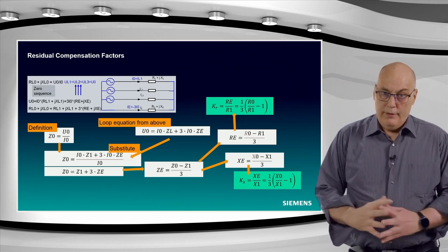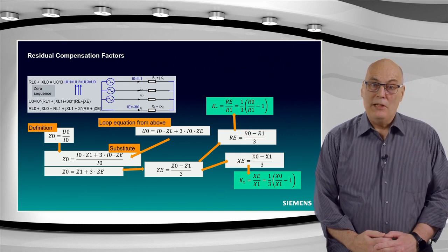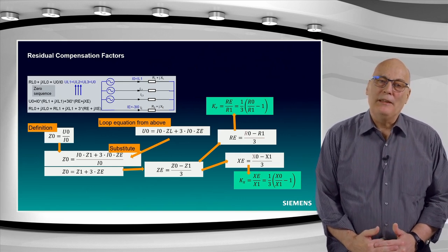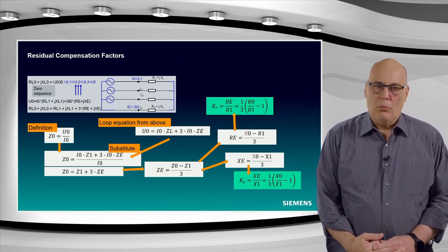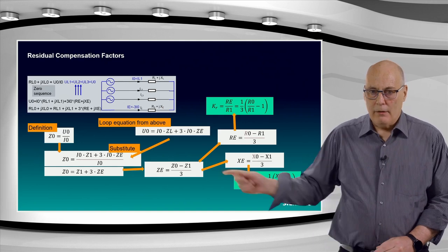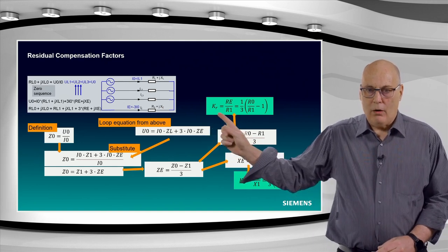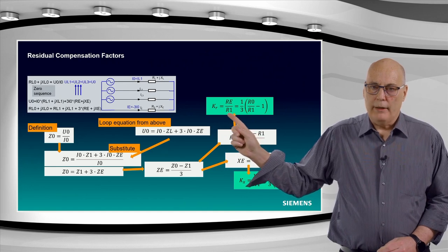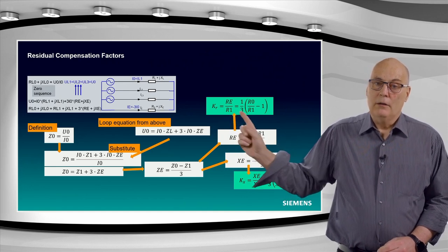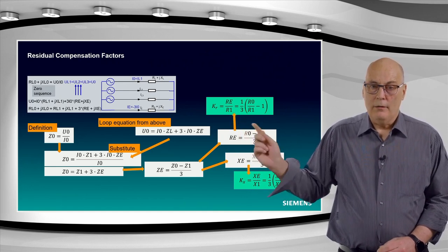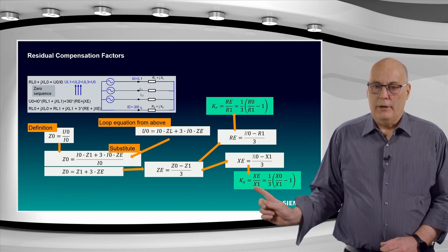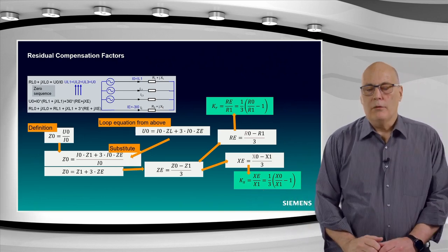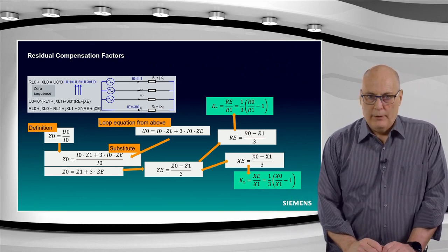And one of the key settings or things that one has to remember in distance protection is the so-called residual compensation factors. It's a name. Maybe you know them better as KR or KX here. Also, sometimes in SIPROTEC 4, you might know them as RE/RL and XE/XL. Well, I showed it here, RE, R1, XE, XL, or XE, X1. Your residual compensation factors, as we know that.